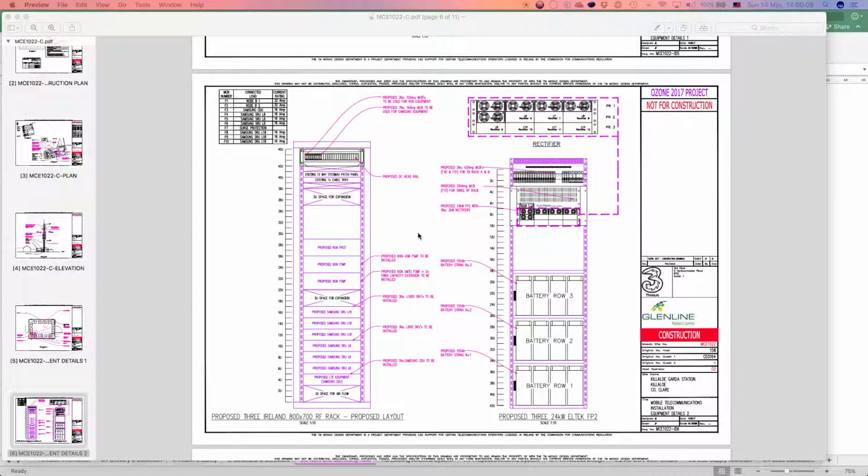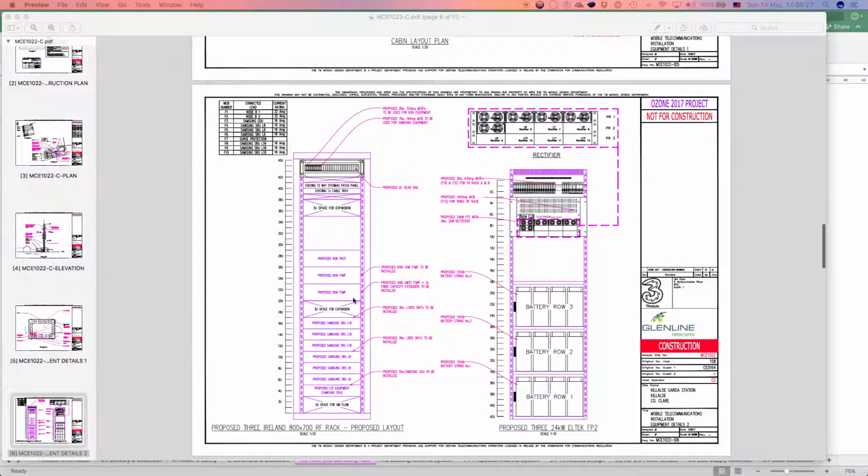So back to the cabin. If you have cabin, you need to show equipment rack, RF rack, and the PSU or power solution rack. Make sure rectifier number is correct, battery strings are correct, and here you show your modules installed, and you show again the breakers. Basically node B breakers are 32 ampere, everything else is 16 ampere.